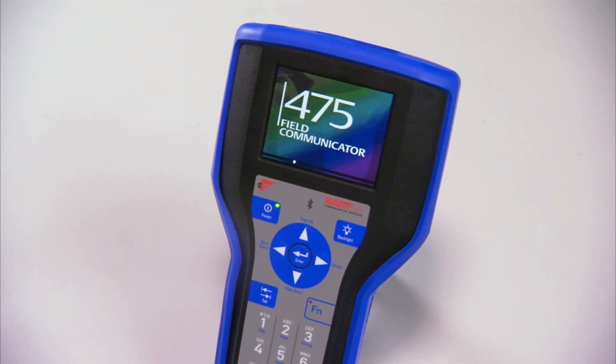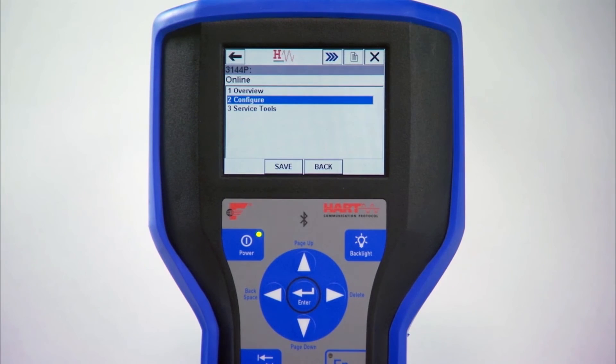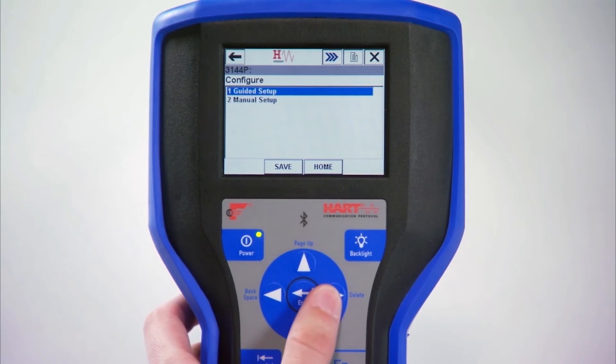First, attach the communicator to the transmitter's power inputs. Note that between 250 and 1100 ohms resistance must be in series for correct functioning. From the home screen on a 475, click Configure, Guided Setup, and then Configure Sensor.